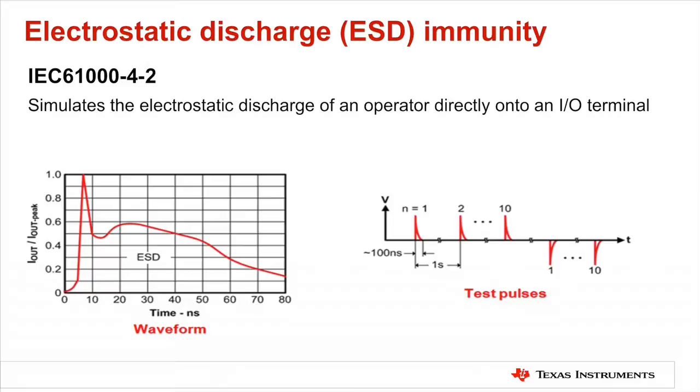Characteristics of this test are the short rise times, short pulse duration of less than 100 nanoseconds, high voltage up to 15 kV, and low current. This test requires a minimum of 10 discharges of each positive and negative polarity. Many equipment manufacturers consider ESD tests the lowest priority of all tests, since its occurrence is limited to installation and maintenance work on I/O modules. During these activities, operators should wear ESD protective clothing and intentionally discharge themselves prior to any contact with the module.